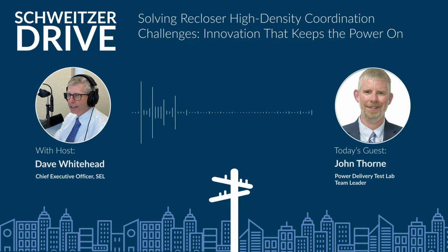That's really the automation piece: how do we get the lights back on after we've isolated a fault to a particular part of the power system. You mentioned one way Alabama Power is going about it is putting in enough reclosers so we can chop up the distribution line, opening up a part of it so only 300 people are affected versus the 3,000 people tied to that distribution feeder. You refer to it as high density coordination solutions for these systems.